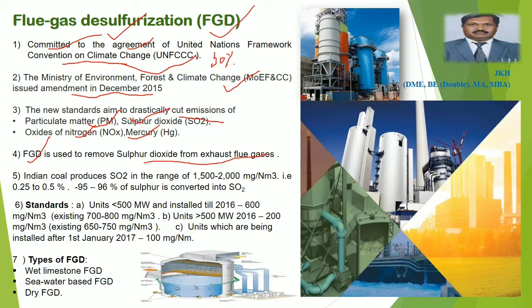Need for FGD: sulfur dioxide emission results in acid rain, corrosion of buildings and structures, and affects human health as well. The range of sulfur content in Indian coal produces sulfur dioxide in the range of 1500 to 2000 milligram per normal cubic meter of flue gas, that is approximately 0.25 to 0.5%. In imported coal, it is more than 0.6%. 95 to 96% of sulfur is converted into sulfur dioxide, and FGD is the technology used to remove this sulfur dioxide from the flue gases.